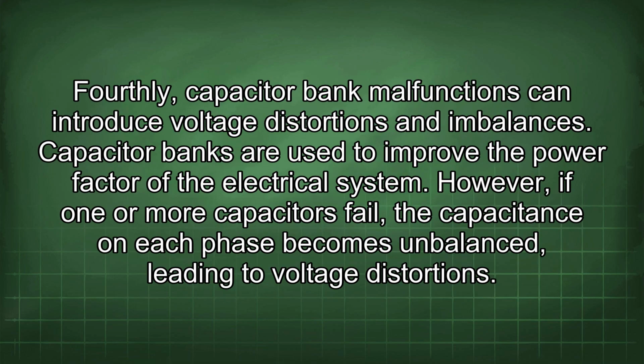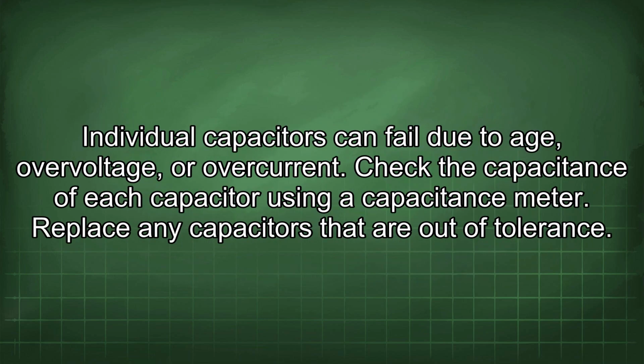Fourthly, capacitor bank malfunctions can introduce voltage distortions and imbalances. Capacitor banks are used to improve the power factor of the electrical system. However, if one or more capacitors fail, the capacitance on each phase becomes unbalanced, leading to voltage distortions. Individual capacitors can fail due to age, overvoltage, or overcurrent.